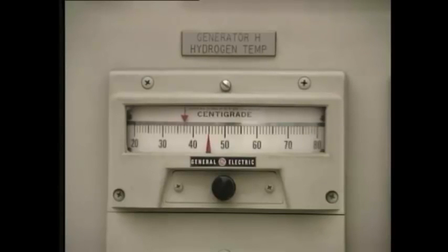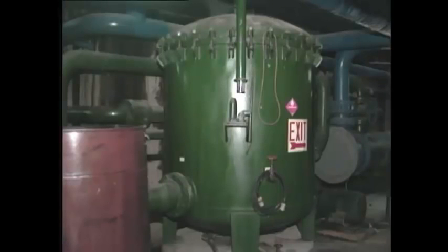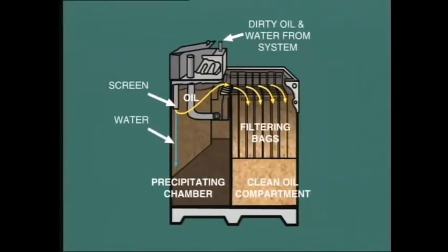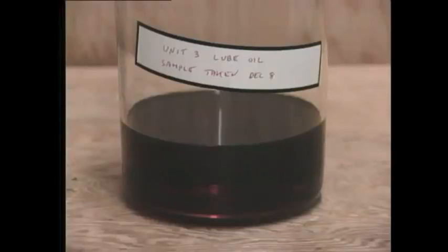More serious yet, the oil is likely to pick up fine pieces of metal and other contaminants in its route through the system. And these contaminants could cause serious damage to the bearings and therefore must be removed. Most lube oil systems include a filtering system within the circuit. This may consist of bag-type filters within the oil tank, or external cartridge filters, or a centrifuge which continuously circulates oil from and back to the tank. Maintaining the cleanliness and purity of the oil is extremely important to good turbine operation. Usually, the lube oil is sampled at regular intervals, say monthly or bi-monthly, and analyzed for impurities and other characteristics.